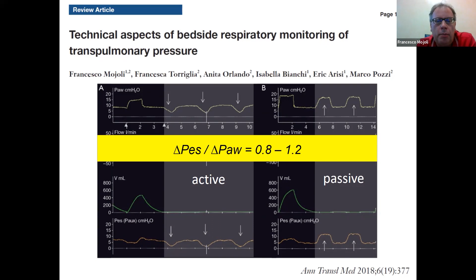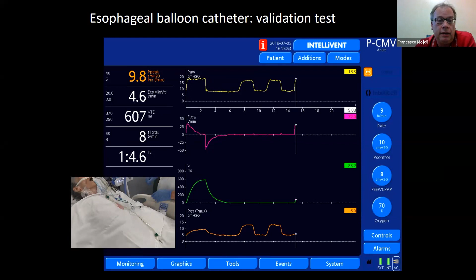And this is an example in a passive patient under pressure control mechanical ventilation. This is the occlusion maneuver and the two gentle chest compressions. After the maneuver, you have to check whether the two swings, the esophageal pressure and the airway pressure swing, are similar, like in this case. So here the test is passed, and when this is the case, it means that the balloon position is okay in your patient, the balloon filling volume is also okay, and your system is able to reliably transmit the respiratory changes of pleural pressure, of intrathoracic pressure.